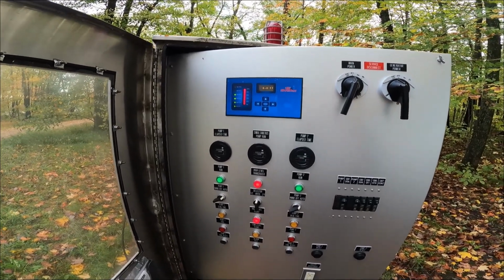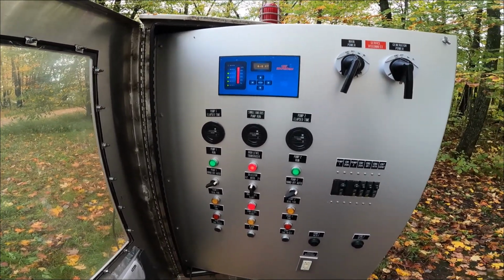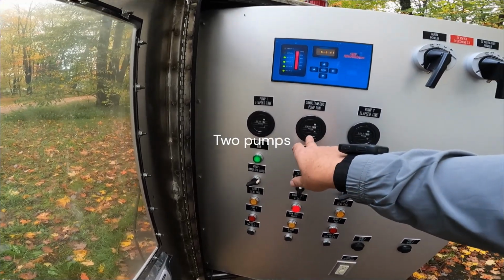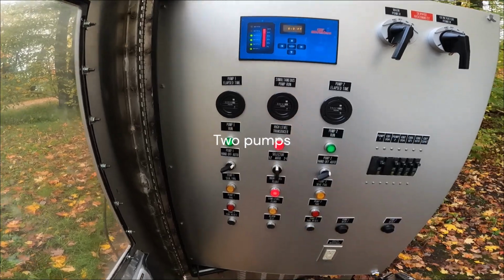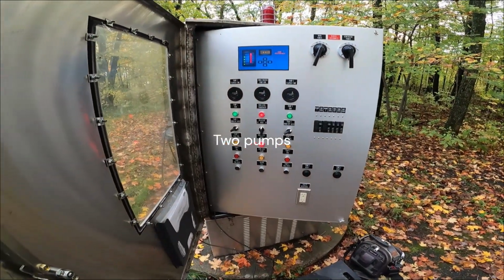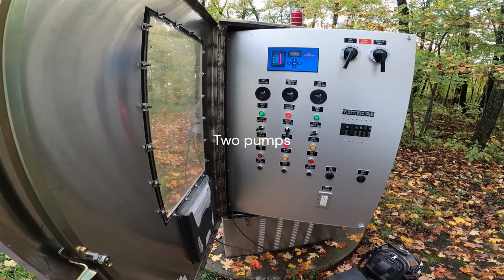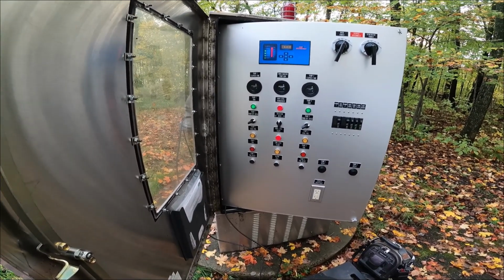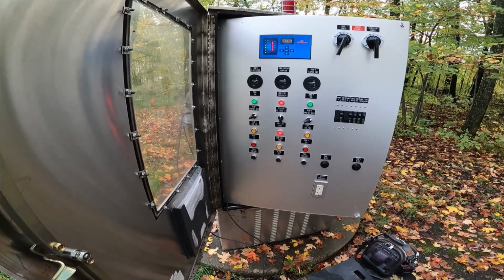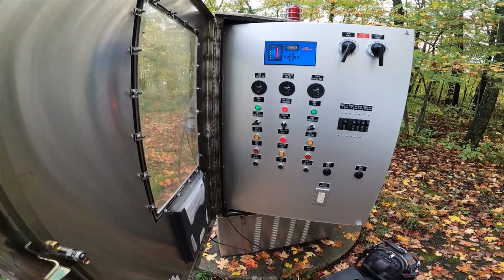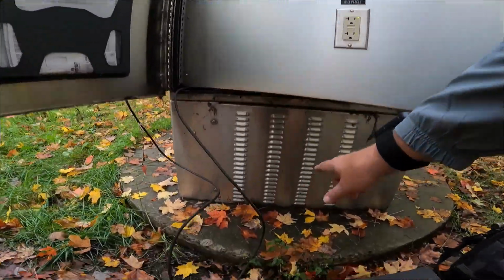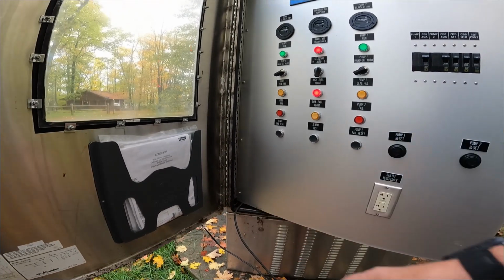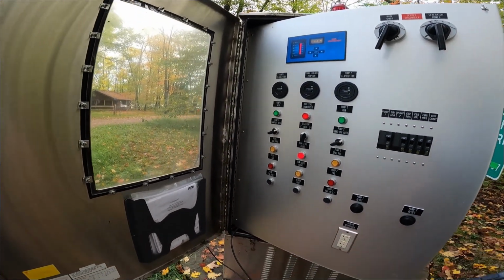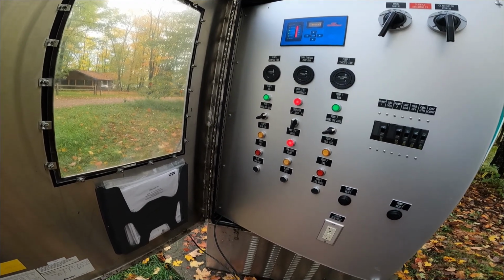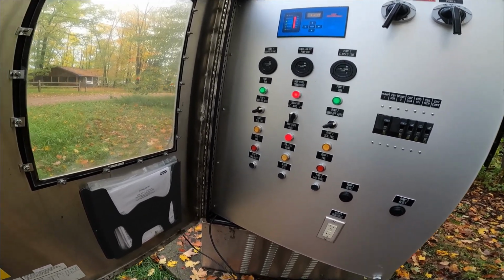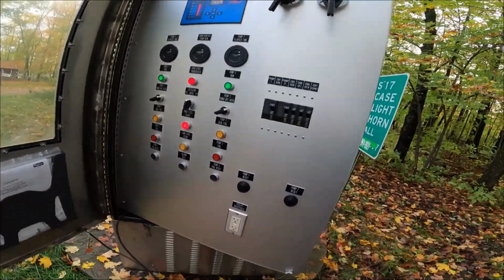And so now we're pulling down, but we've got to empty the sewer pipe out too. This time meter here is showing that we're running all three pumps. All right, so now I've kind of proven to myself that I need a new transducer. So what I think I'll do now, while we're pumping down, is take this panel off right here so that I can string this cord around and get it up temporary, because I'm not going to keep this one here. This transducer is just a temp one. I'm going to get a brand new one to put in this station. So let's do that.